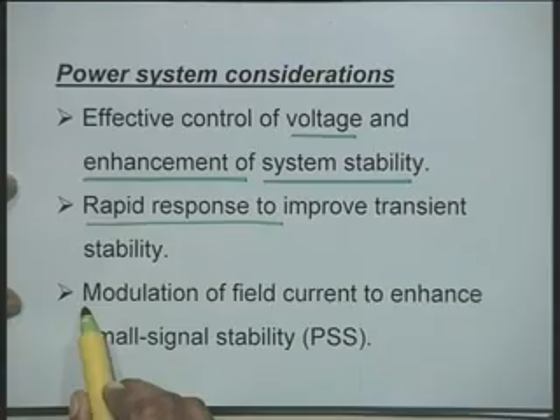Then we should have a provision to modulate the field current to enhance small signal stability. That is, whenever there are some perturbations taking place, oscillations are created in the system. The system is never in a steady state condition, it is always in a quasi steady state condition, because load changes are taking place continuously. Whenever load changes take place, generation changes, and in this process the system is in a dynamic condition. And there are always small oscillations in the system. When I say small oscillations, the magnitude of oscillation is small and the frequency is low.